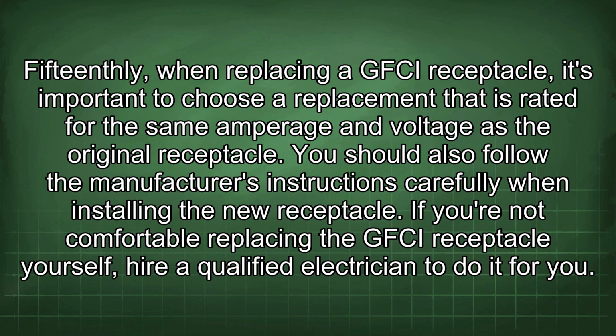15thly, when replacing a GFCI receptacle, it's important to choose a replacement that is rated for the same amperage and voltage as the original receptacle. You should also follow the manufacturer's instructions carefully when installing the new receptacle. If you are not comfortable replacing the GFCI receptacle yourself, hire a qualified electrician to do it for you.